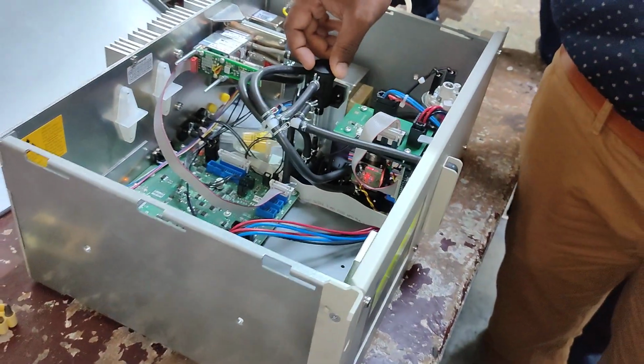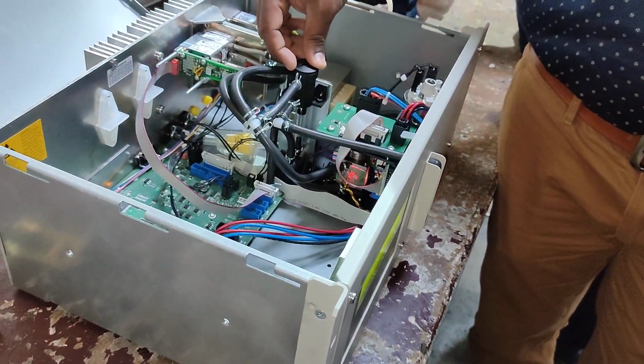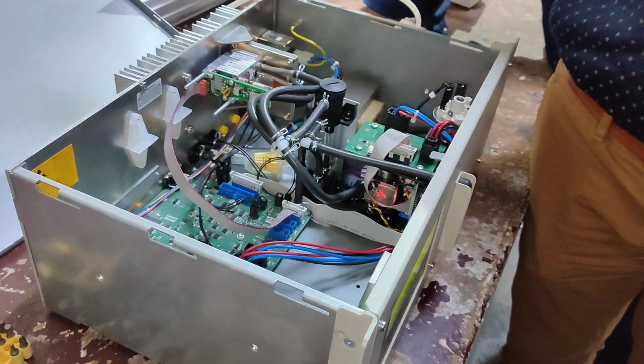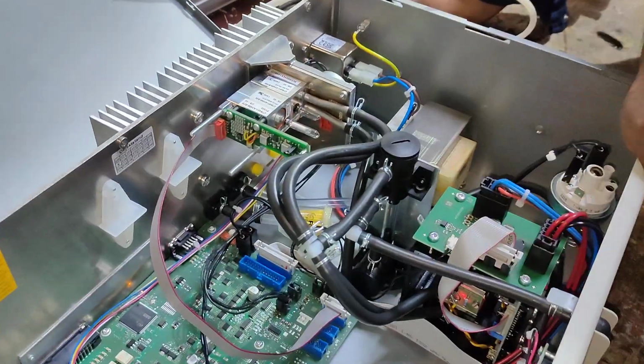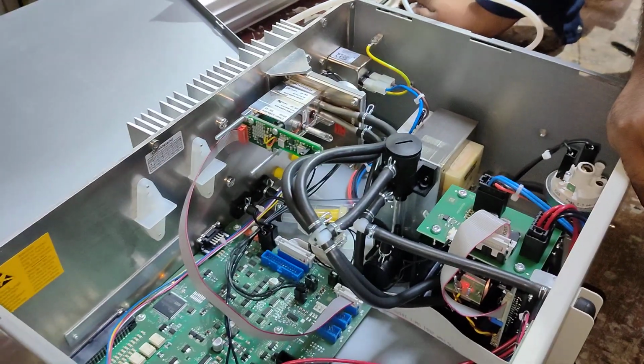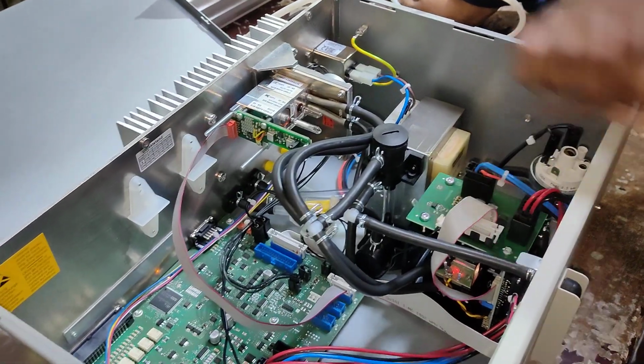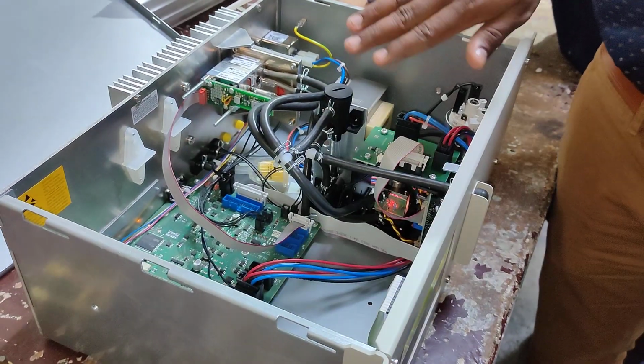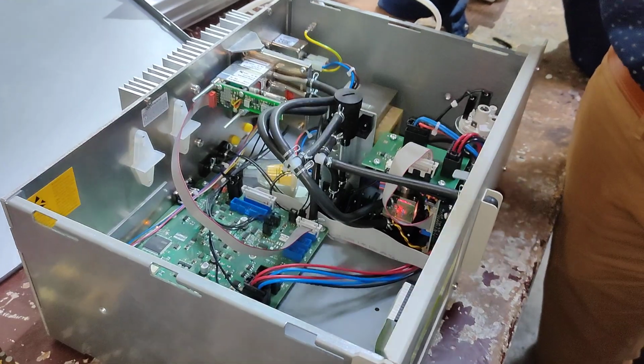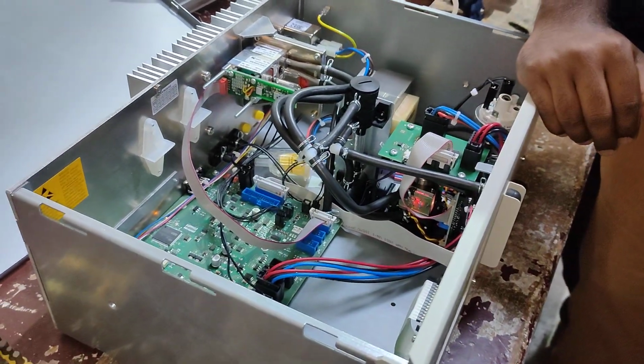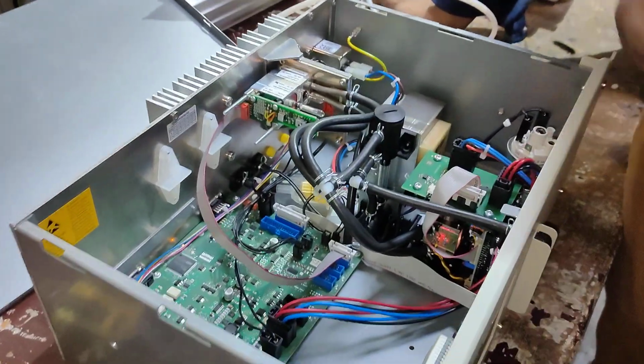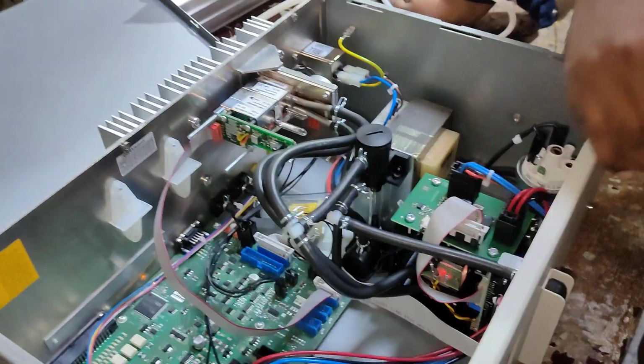If we need to clean it, do we just open this top? Is there any side filter available inside? No. What you have to do is just run the air, and it will get cleaned up. There is nothing inside. The sample will not flow down, it will only flow up, so the water will go down because the sample is lighter, and the sample will flow through the other tubes.